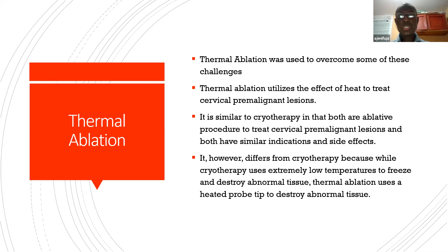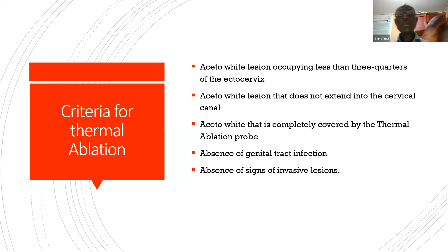But then, people that have been in the field using these devices have actually modified them. For example, look at the first criterion there, which is that the lesion must occupy less than 3/4 of the ectocervix. Actually, that applies strictly to cryotherapy. But with thermal ablation, even if the lesion is very large, you can coagulate different points of the ectocervix. The second one is that the acetowhite area must not extend into the cervical canal. Well, that is the general rule. But if you can see the upper limit of the acetowhiteness, you can actually use thermal ablation.